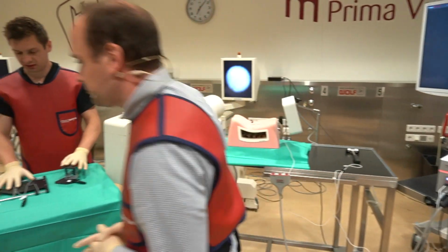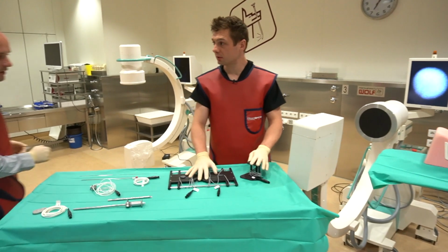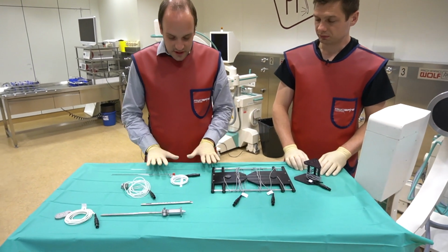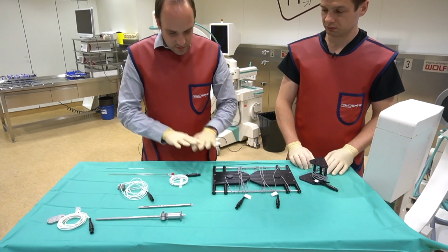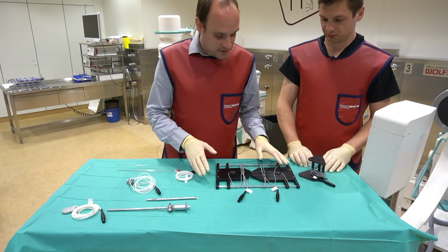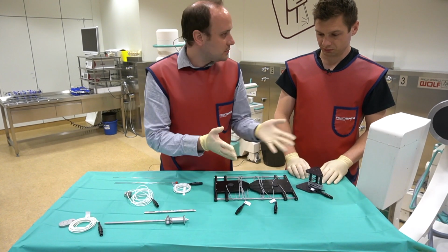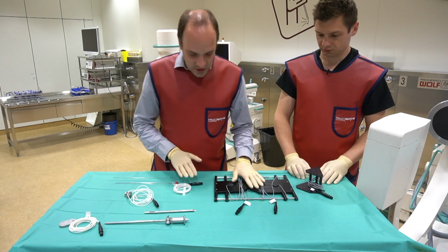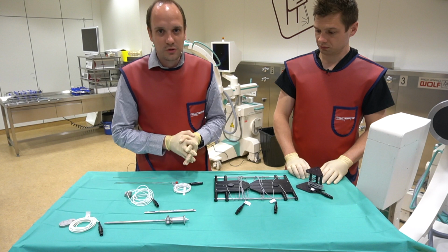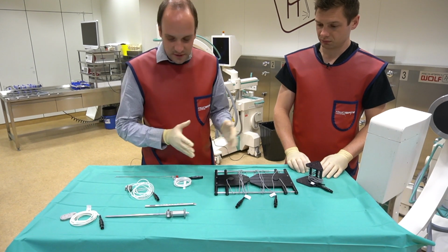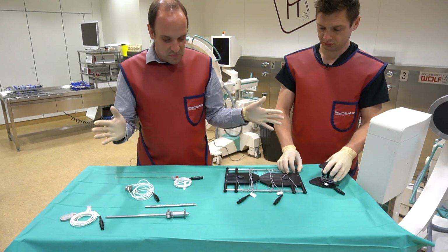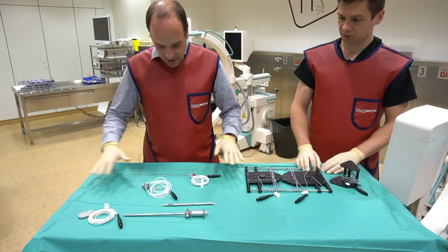So Frank, is this sterile, non-sterile? Is it reusable, single use, or what? All of what we have here on the table can be sterilized with the autoclave. And so it can touch the patient at any time. Just if it's unsterile, we cannot place it again. But of course, there's no need to plug it again if you do it correctly the first time. Then they are reusable as much as you like. So all of the things are reusable.